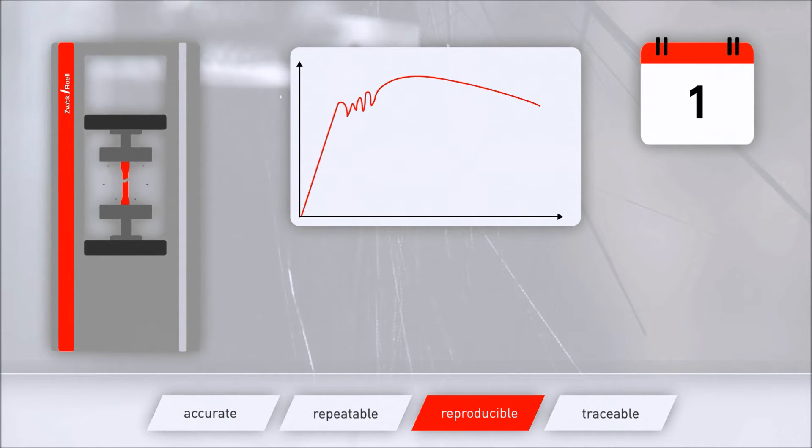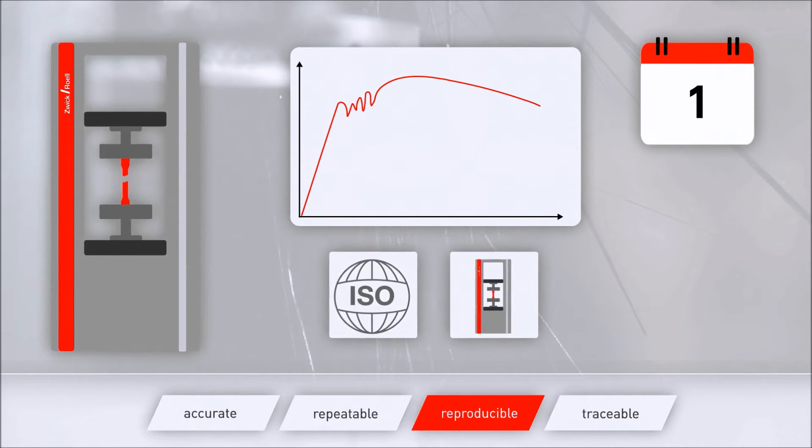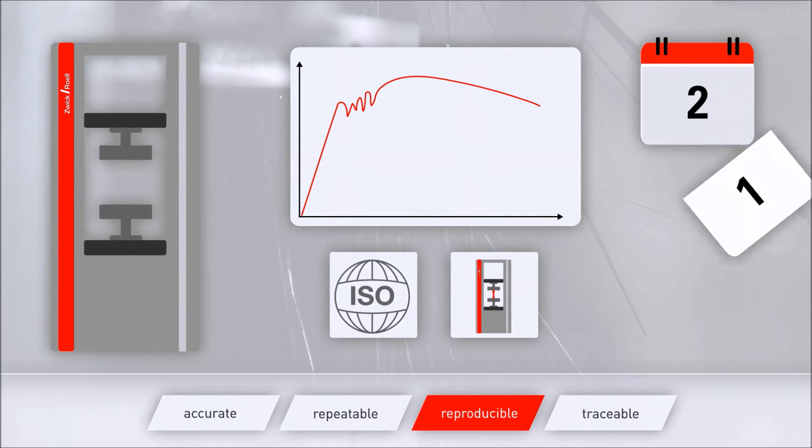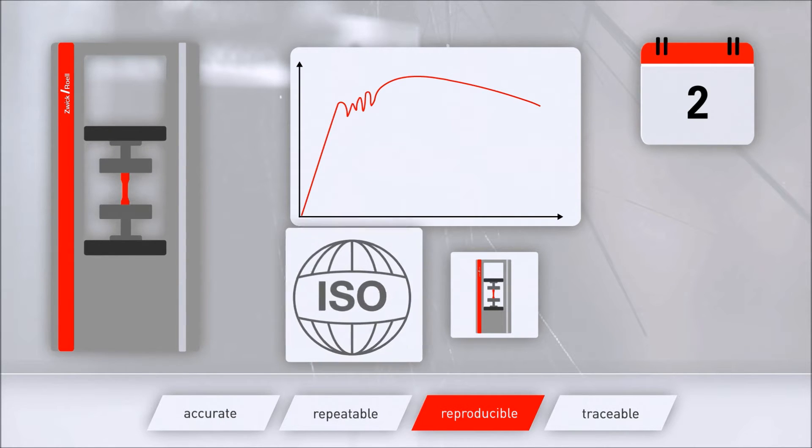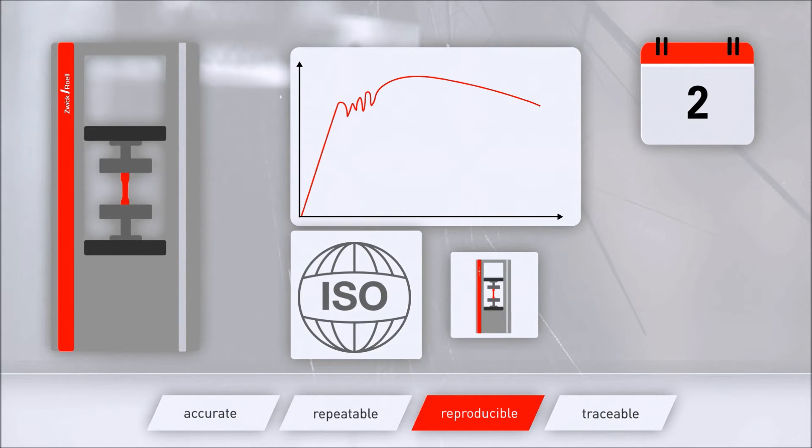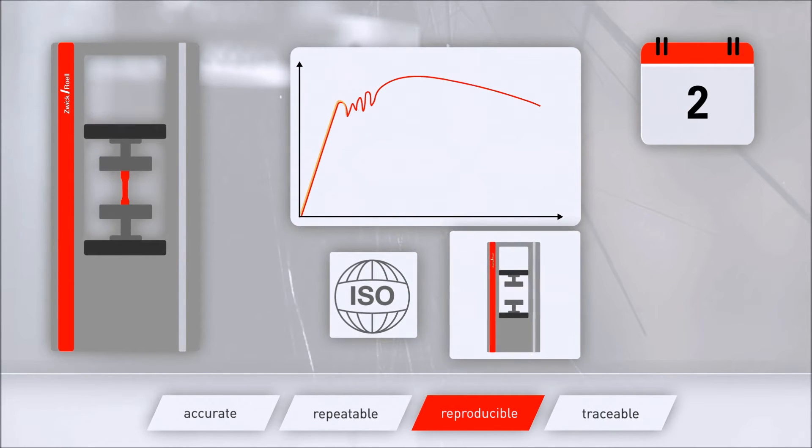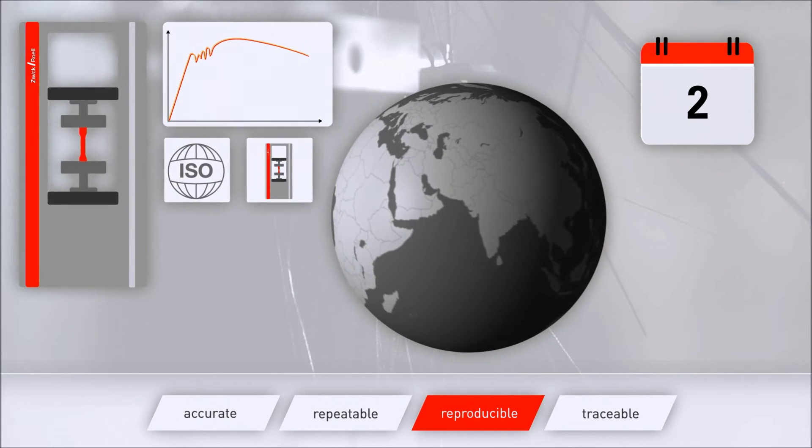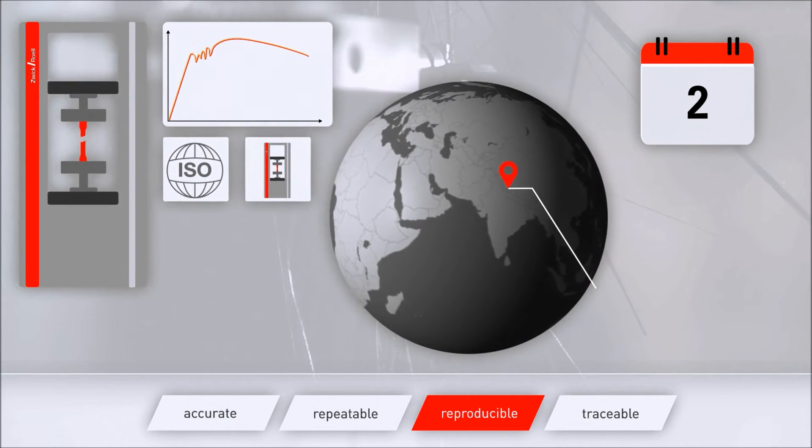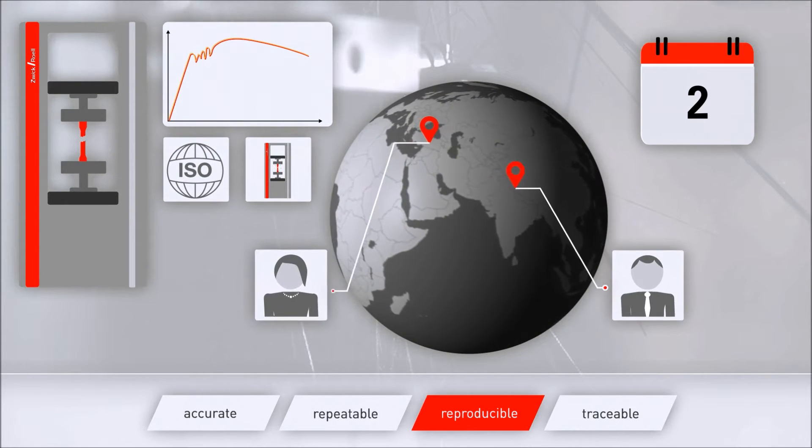Reproducible is precision under reproducible conditions. This means the same measurement procedure and similar measuring equipment, generally at different locations, multiple operators and test conditions, as well as performing the measurement over a lengthy period of time.